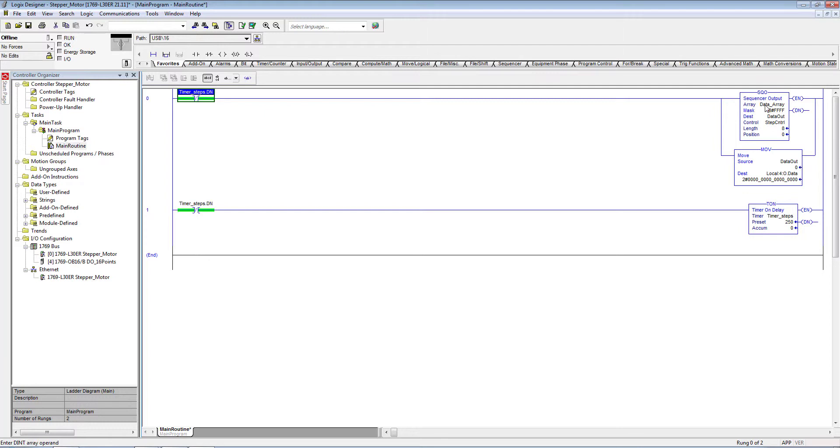The sequencer output instruction is reading this data array elements one by one based on every next interval which is set by this timer at 250 milliseconds. When it's done for 250 milliseconds it energizes this rung and the first element or next element of the array will be copied to this data output variable.